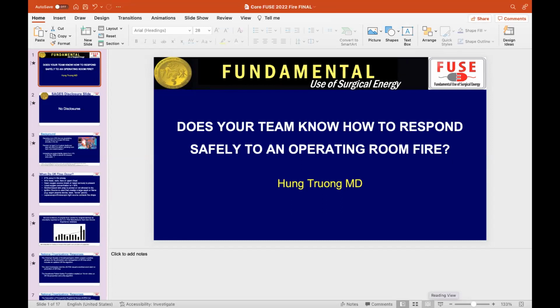And the active electrode has an equivalent amount as the dispersive electrode - the same amount of voltage and current is going through the active and dispersive electrodes. Both those cords need to be coming from the feet, need to be away from the cardiac implanted device. Okay, if you understand those, I think you're going to bat 100% on the FUSE questions.